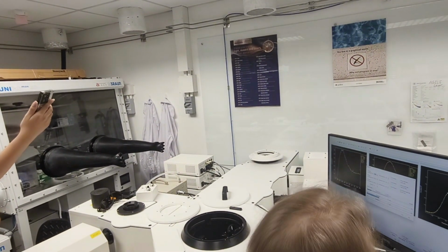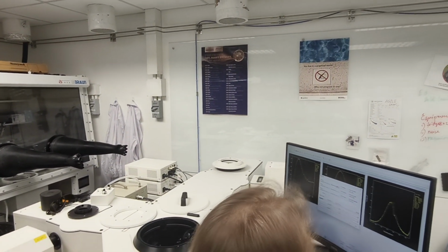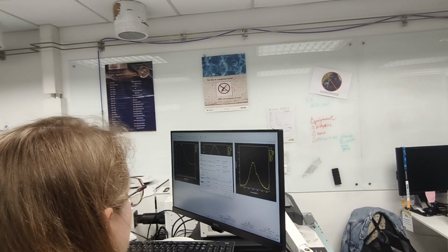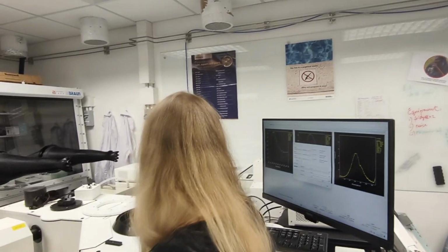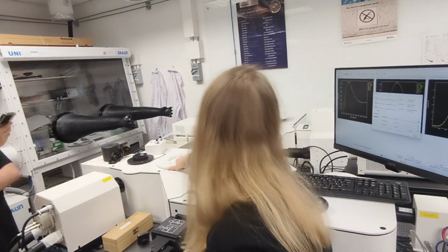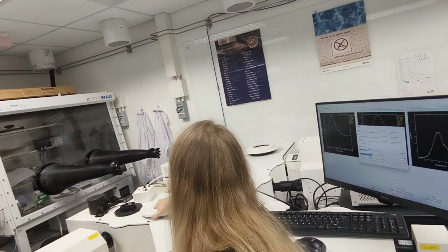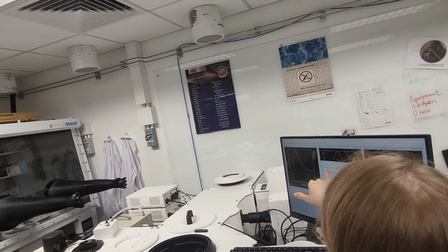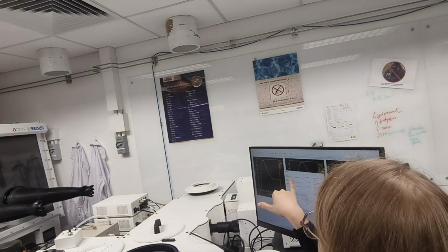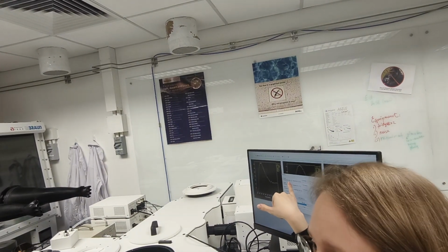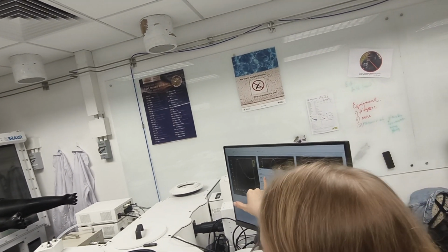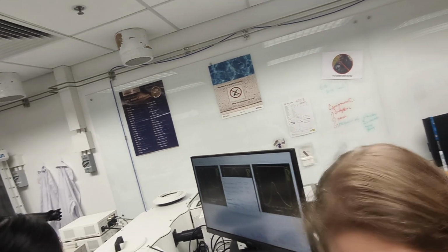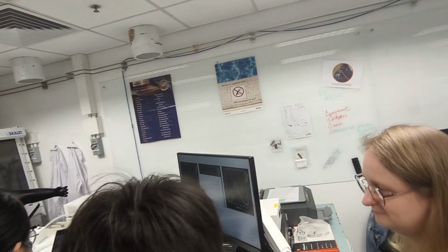If I open it, just to demonstrate what a monochromator actually does, I can open it. No, I can't. Oh yes. So I told the diffraction grating to move to a certain position and to show me blue color. I know that it will be around 450, and you can look inside. It defined exactly blue color.